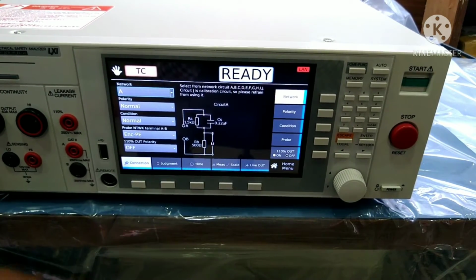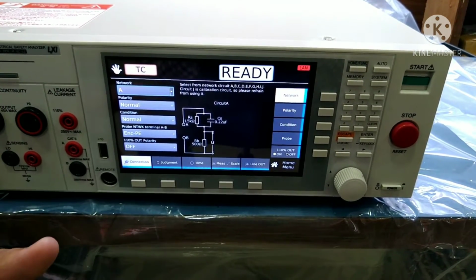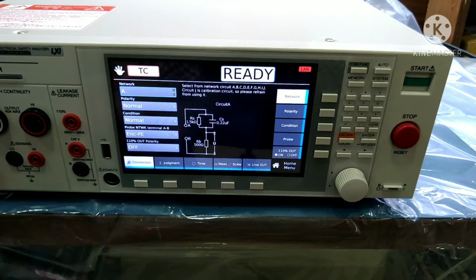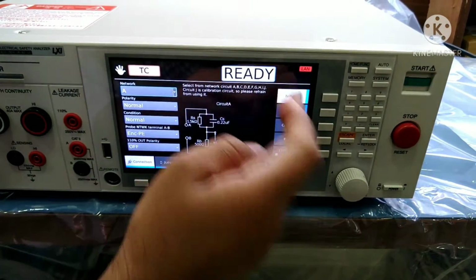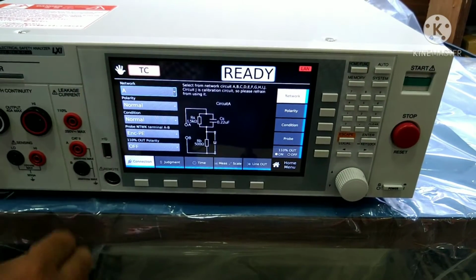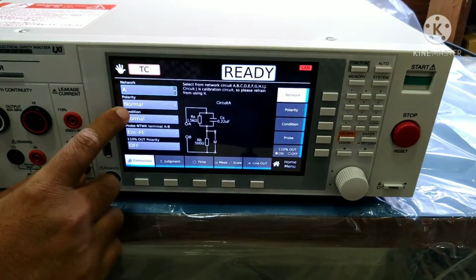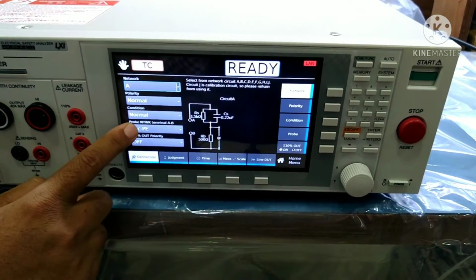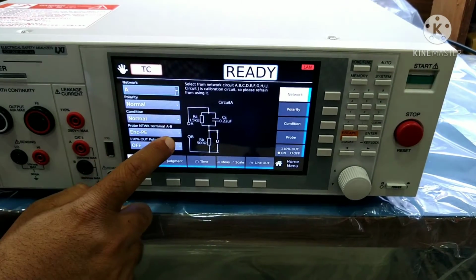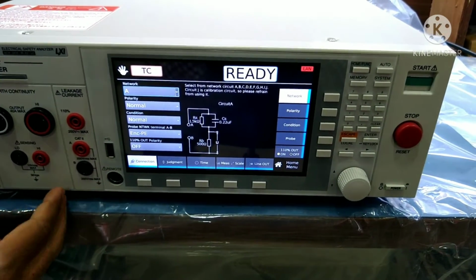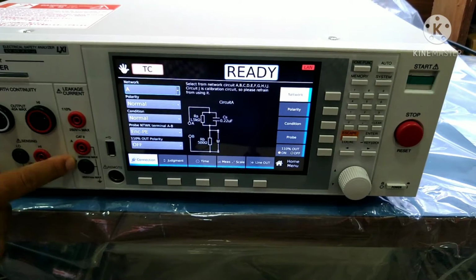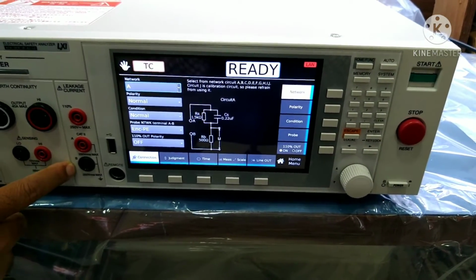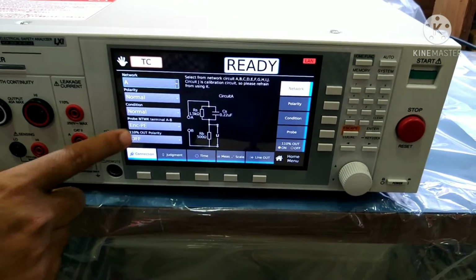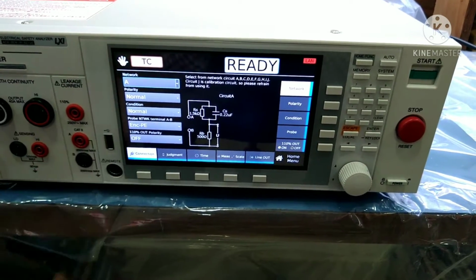Later on we will implement one circuitry, and I will show you how you can test it by using this LC circuitry. So this is the basic setting of the TC. This is network type A. Polarity will be normal; you can change it as per your requirement. This is the probe position. We have these probe positions: this is A and this is B. So probe AB position will be enclosure and the PE in between.